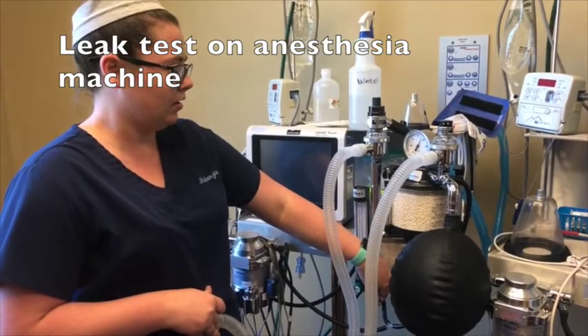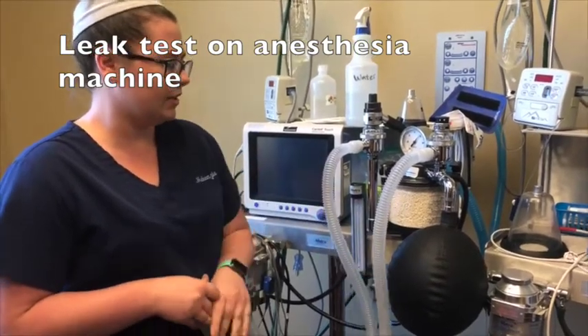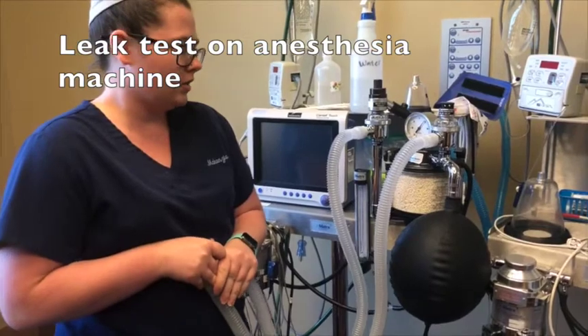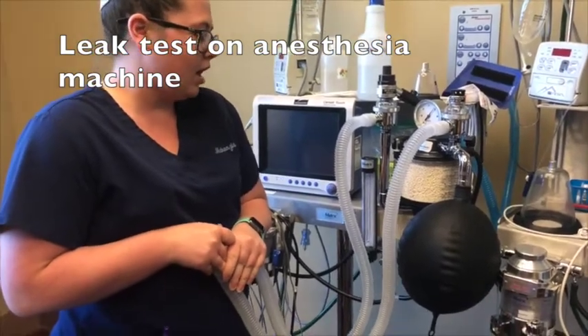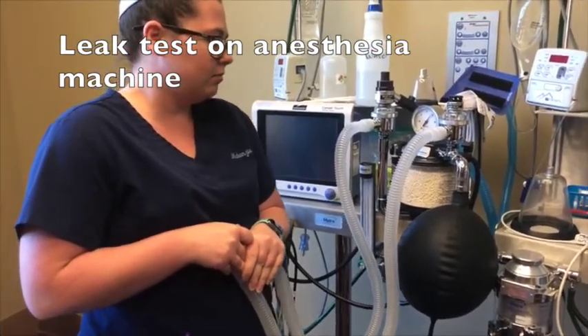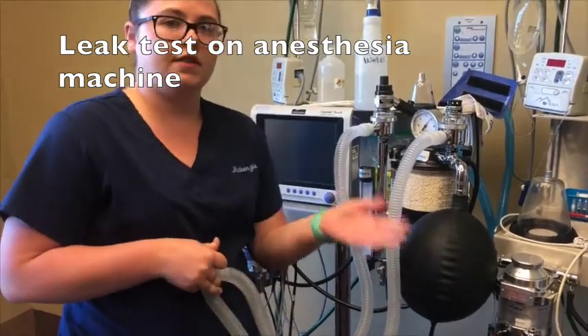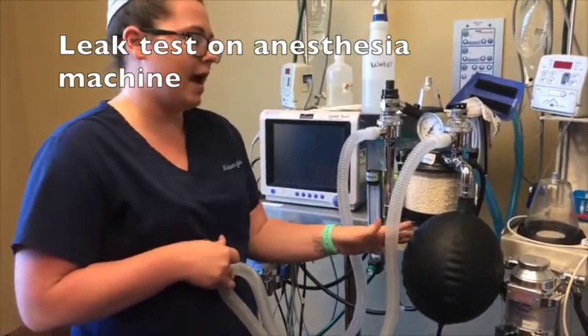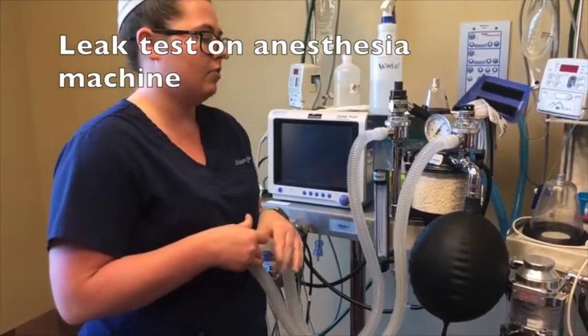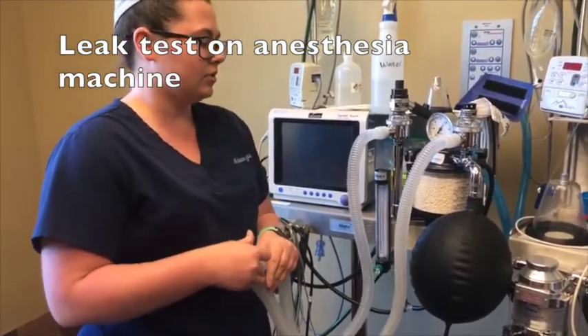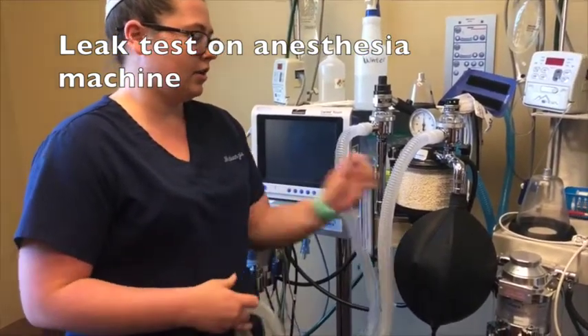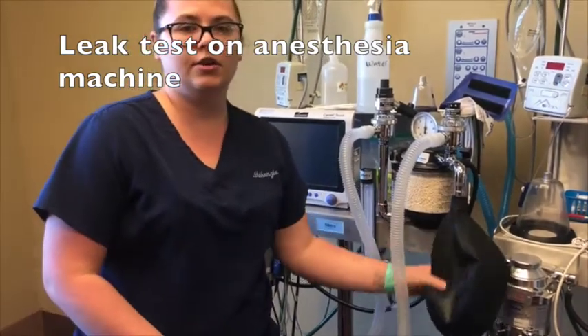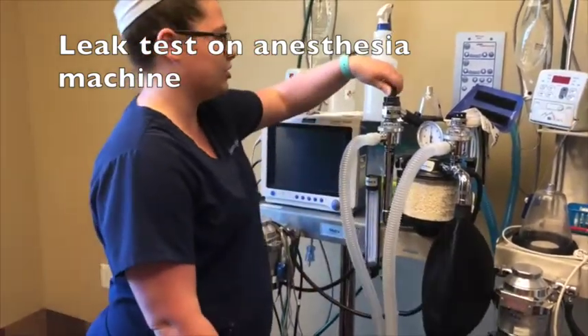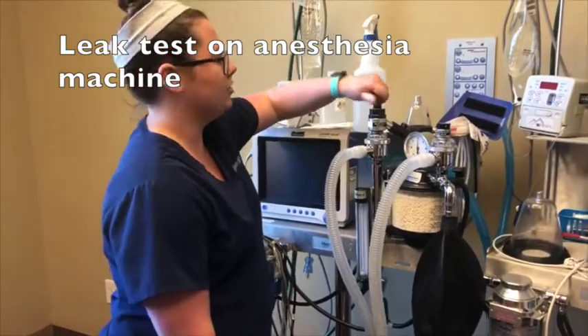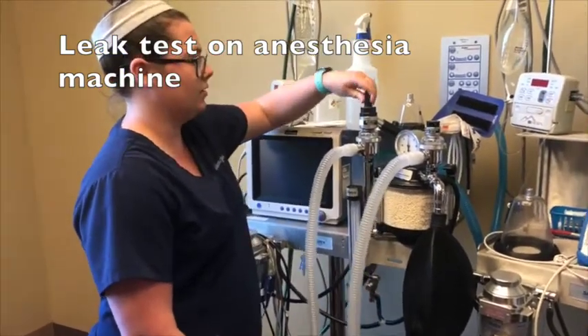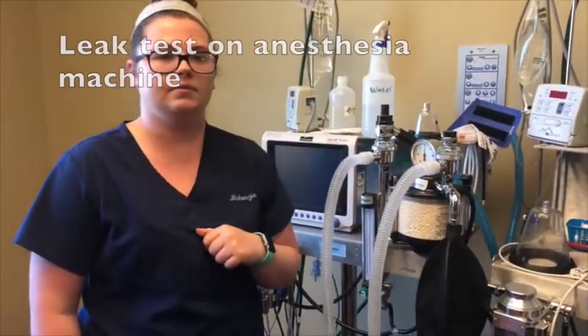Okay. And we're going to hold it there for about 10 seconds and make sure nothing's leaking. So since the bag's not moving, it's not going down at all, it's staying the same size, that means nothing's leaking out of it. So this bag is good for surgery. And then once you finish your leak test, you just release, and that's how you know your bag is good to do for surgery. And then the biggest thing, you just want to make sure you put that pop-up valve back to where it was. And that's how you do a leak test.